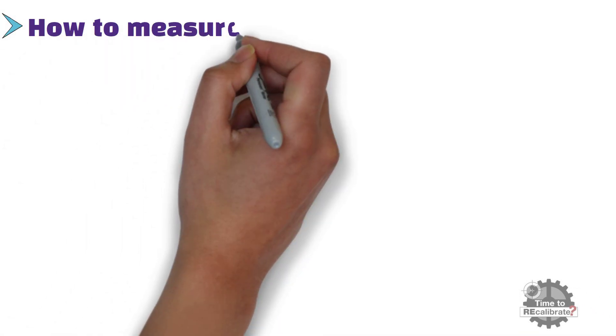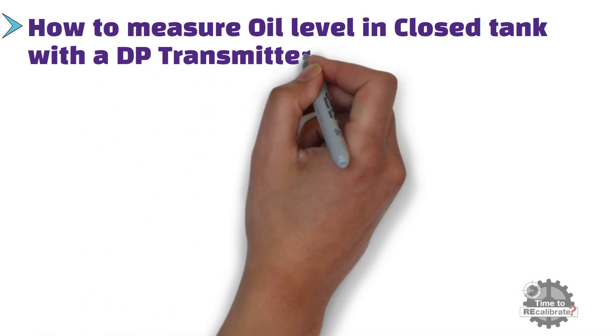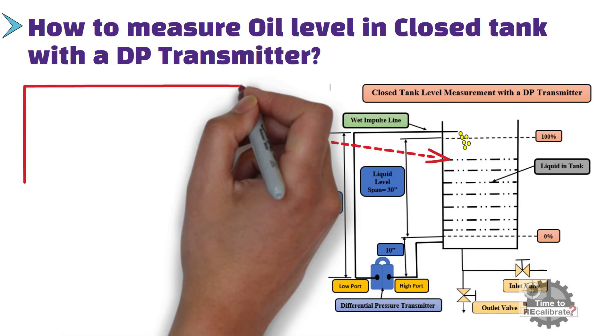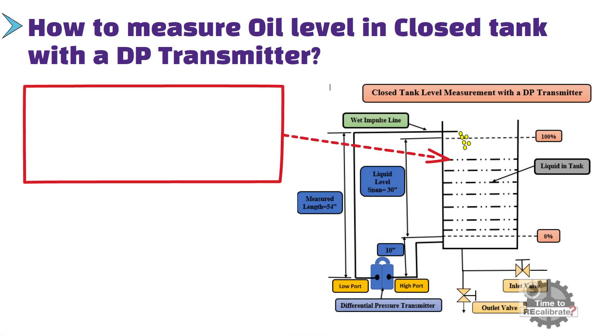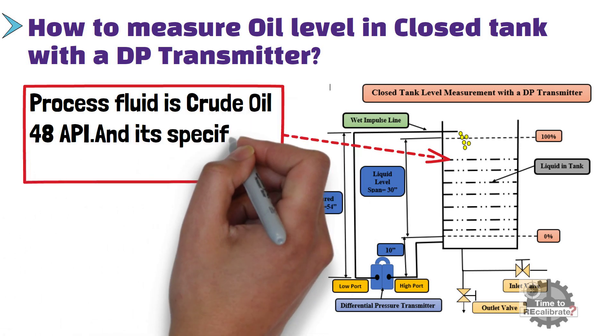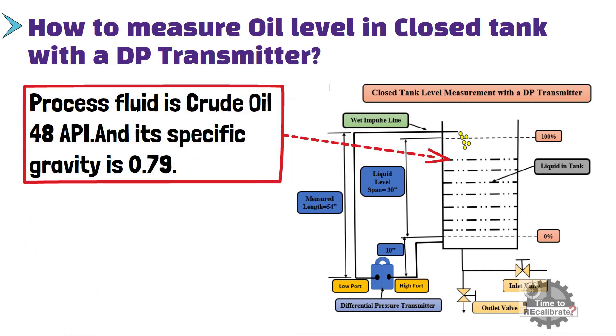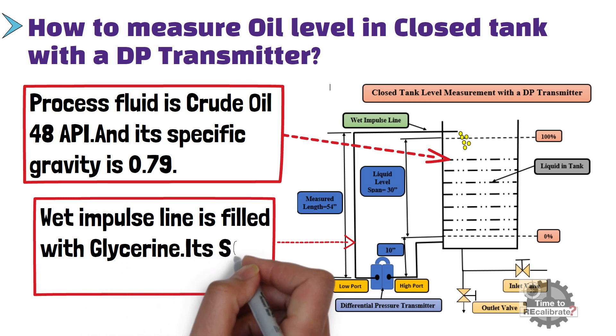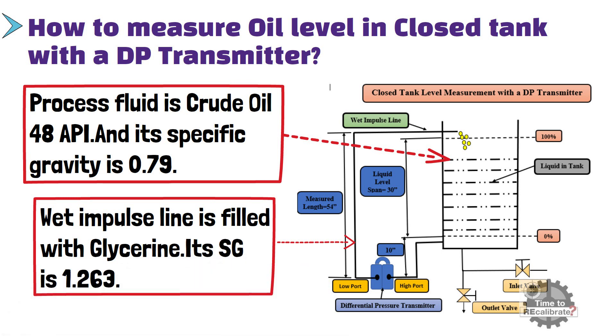Now, how to measure oil level in a closed tank with a DP transmitter? Let's assume the process fluid is crude oil 48 API, with a specific gravity of 0.79. Let's also assume that the wet impulse line is filled with glycerin, and its specific gravity is 1.263. The remaining conditions are the same as the previous example: the DP transmitter is installed 10 inches below the 0% baseline, and the height of the wet impulse line is 54 inches. Now let's go to the calculation table.